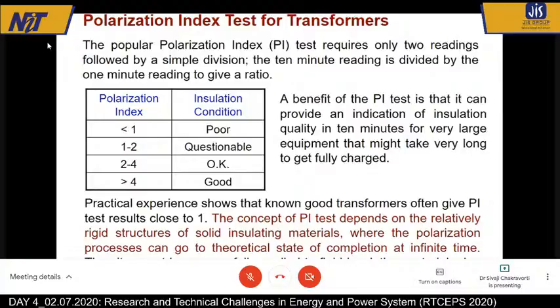So if we divide the 10 minute insulation value by the 1 minute insulation value, it will be greater than 1. So this is a table which is given by Megger actually, that for a transformer, if it is less than 1, it is very poor condition. If it is 1 to 2, it is questionable. 2 to 4 is okay. Greater than 4, good.